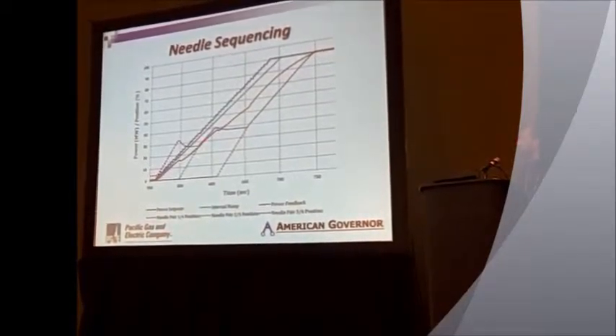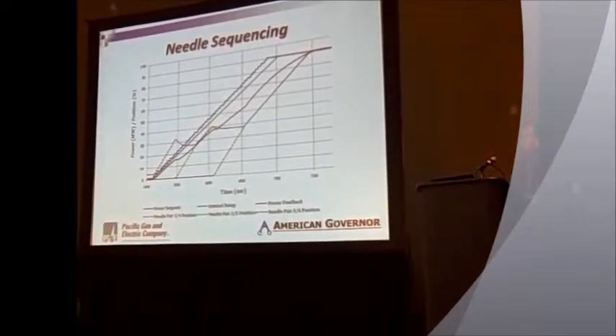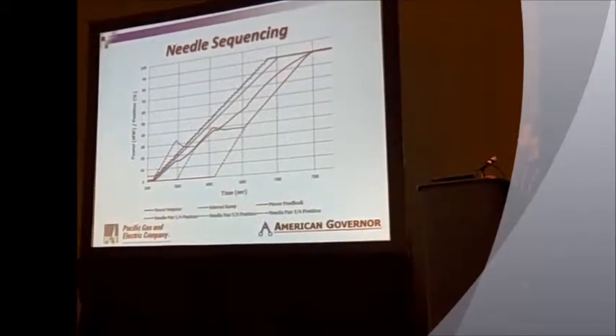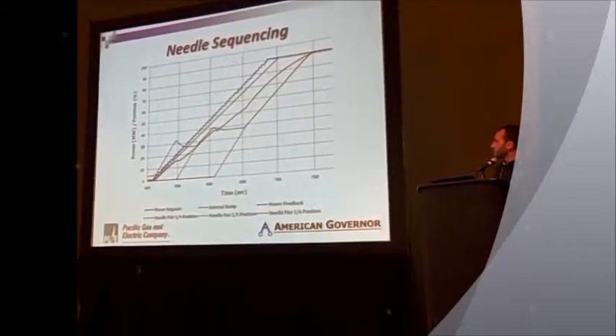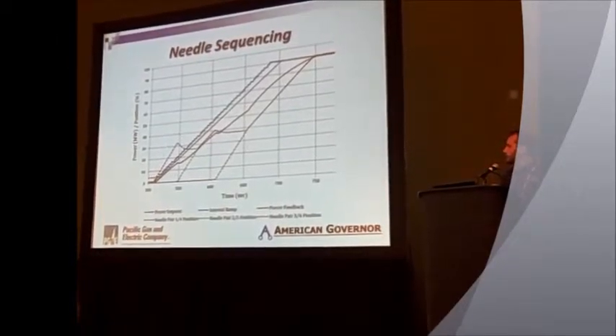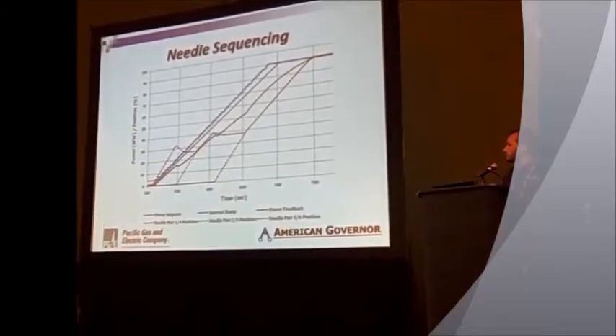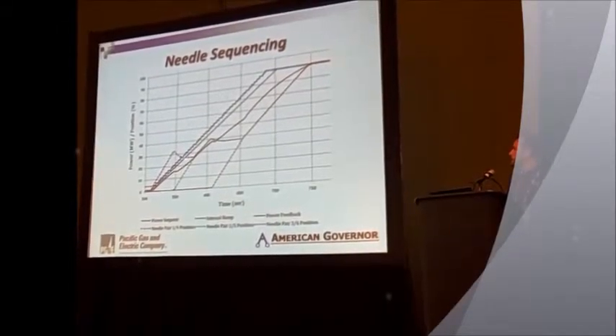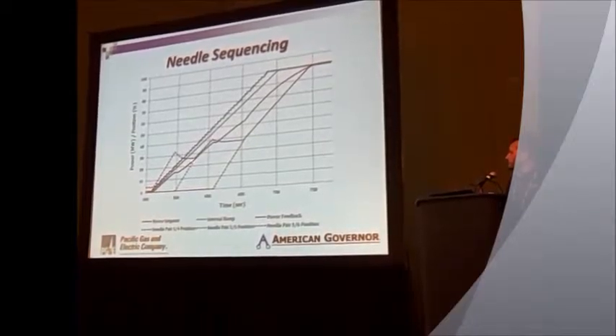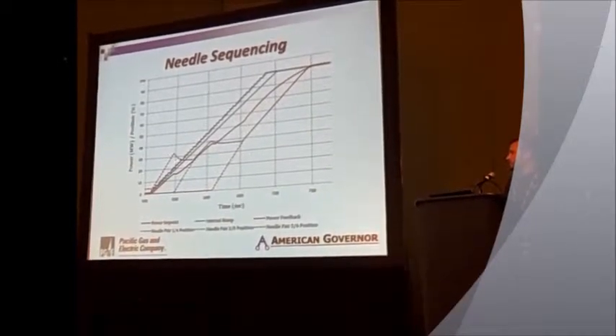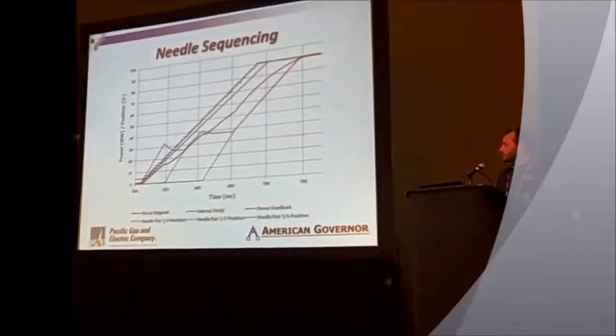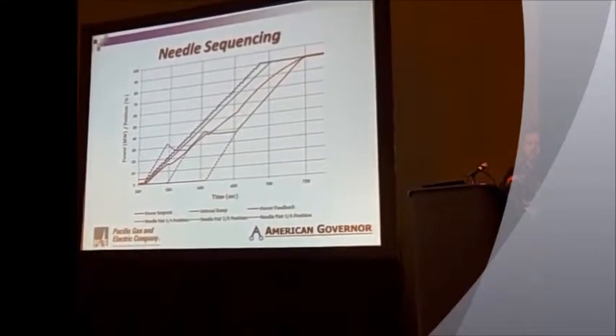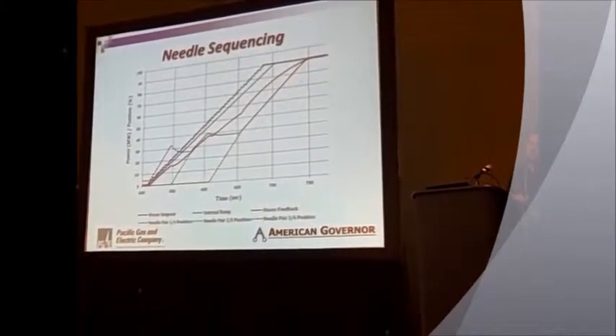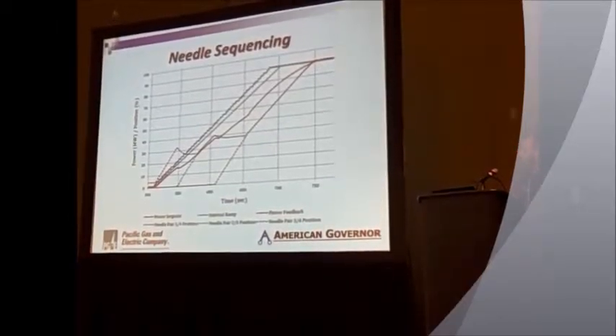Now, what you're looking at in the dashed lines are the 3 needle pairs. The blue would be the first and fourth needle, green would be the second and fifth needle, and red would be the third and sixth needle. So the first needle pair is ramped up until the set point crosses the transition boundary, at which point the second pair would ramp up at a fixed rate, and the first pair would control on its own under PID control to maintain constant flow changes through the needles, and therefore constant megawatts. And again on the next transition.